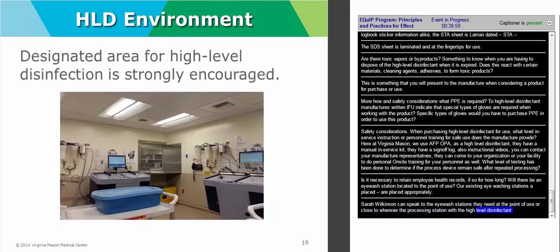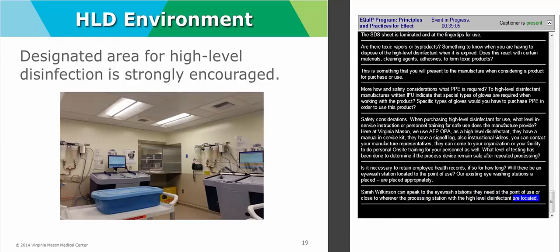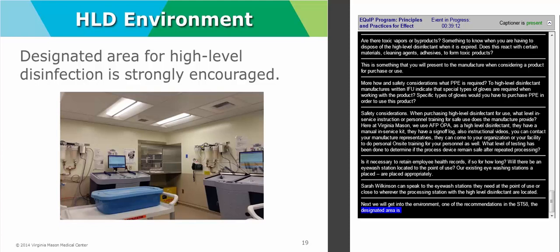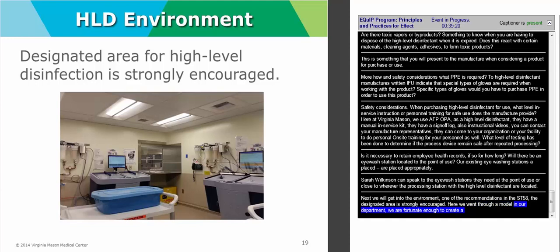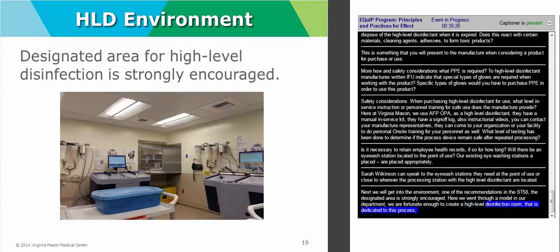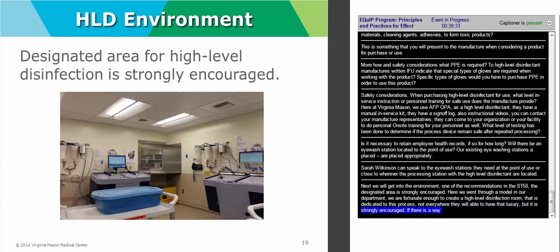Next, we'll get into environment. One of the recommendations in the ST58 is that a designated area for high-level disinfection is strongly encouraged. Here, we went through a remodel in our department, so we were fortunate enough to create a high-level disinfection room that is dedicated to this process. I know not everywhere will have that luxury, but if there's a way to separate a barrier or a section of the department dedicated specifically to this, it is highly recommended.